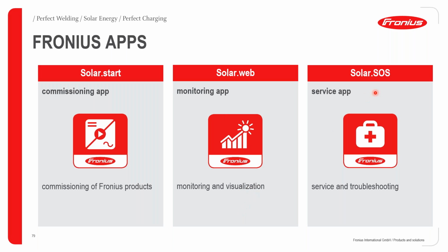Also, something that is very important for installers is Solar.sos, or the Solar Online Support. This is a service app that allows all our installers to troubleshoot their systems without necessarily making a call to Fronius. In the past, you required a customer number to register for this Solar.sos service. But now, because we have it available as a phone app, all you need is to go through a registration process once you download it, and you can diagnose all the faults that you may encounter with your inverters without having to contact Fronius tech support. That ensures the uptime of the systems you have installed is as high as possible. So please check the app store on whichever phone you're using. You can easily download all of these apps, and they are going to be very helpful for your installations.